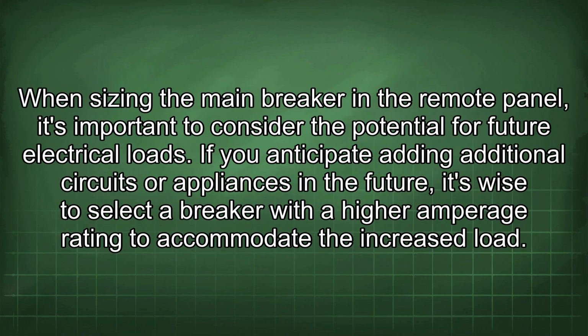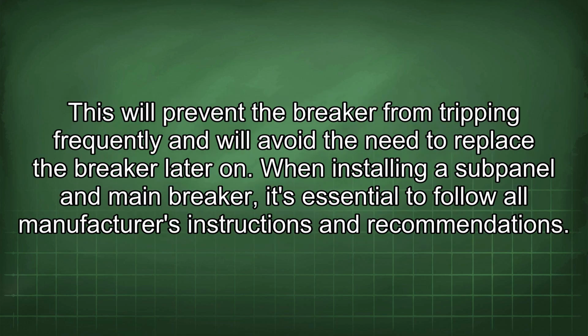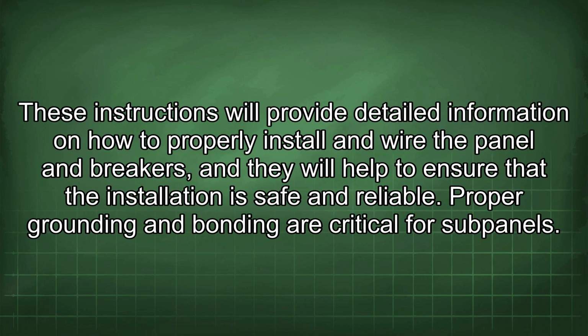When sizing the main breaker in the remote panel, it's important to consider the potential for future electrical loads. If you anticipate adding additional circuits or appliances in the future, it's wise to select a breaker with a higher amperage rating to accommodate the increased load. This will prevent the breaker from tripping frequently and will avoid the need to replace the breaker later on. When installing a subpanel and main breaker, it's essential to follow all manufacturers' instructions and recommendations. These instructions will provide detailed information on how to properly install and wire the panel and breakers, and they will help to ensure that the installation is safe and reliable.